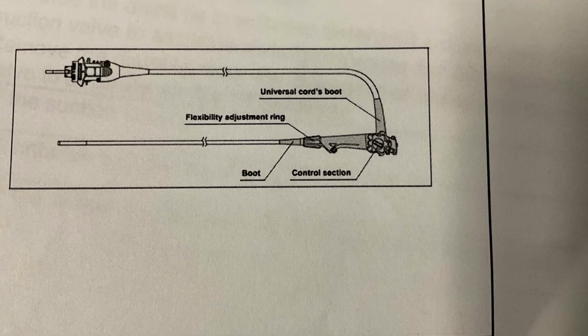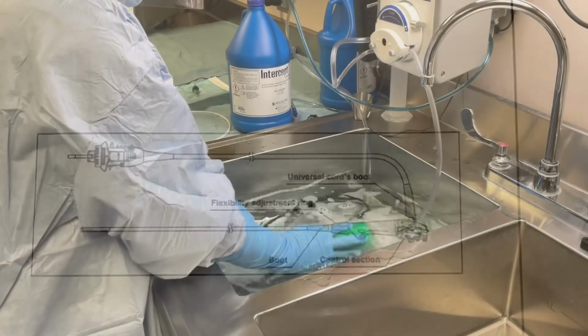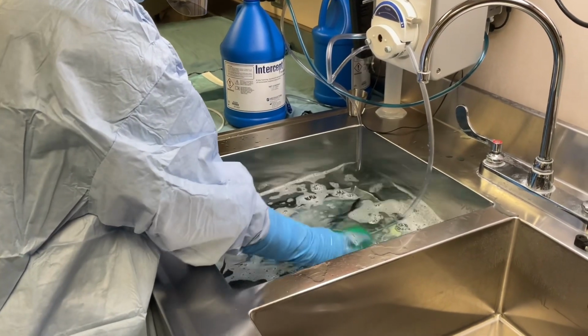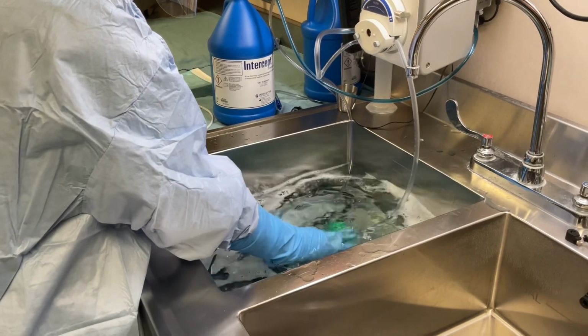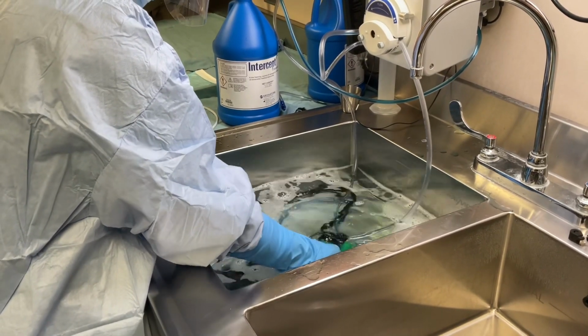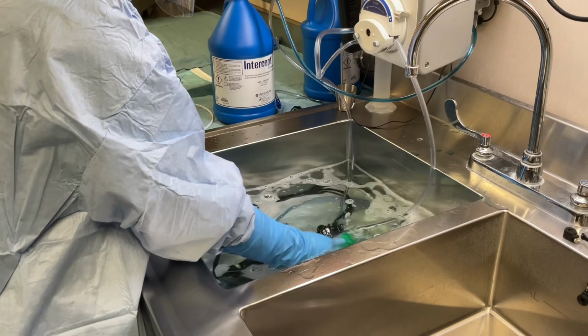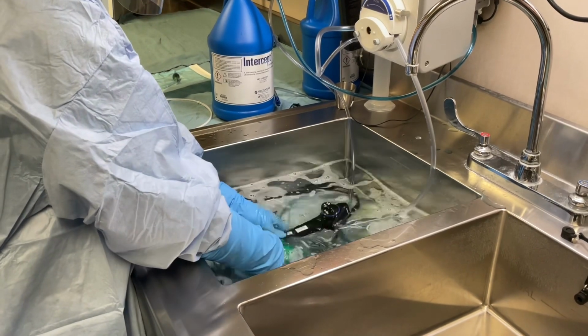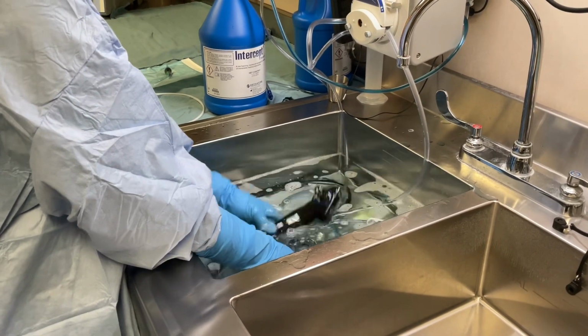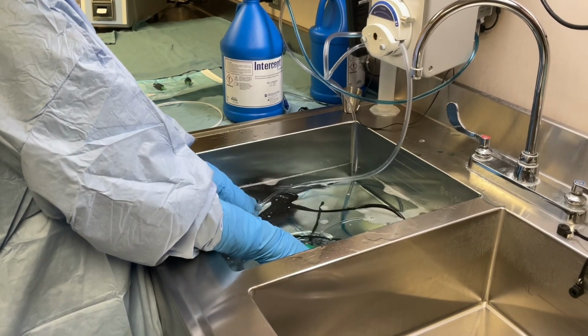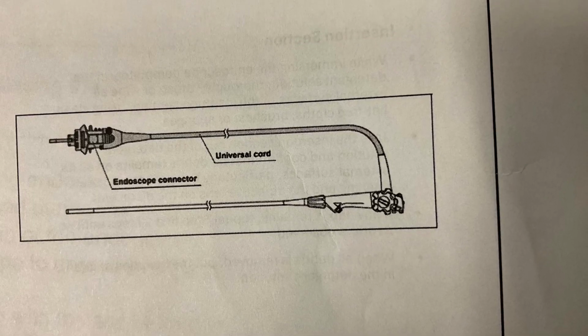While immersing the endoscope completely in detergent solution, thoroughly wipe all external surfaces of the control section using a lint-free cloth or sponge. Verify that no debris remains. If so, repeat steps. Finally, we'll move on to the endoscope connector and universal cord.